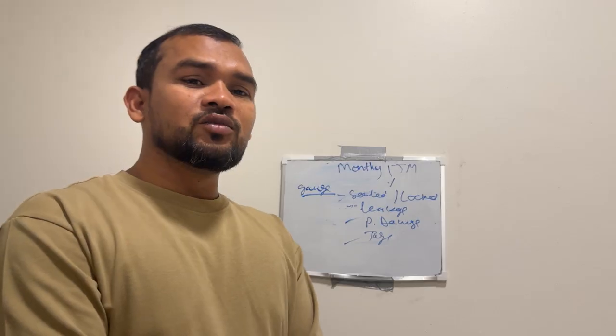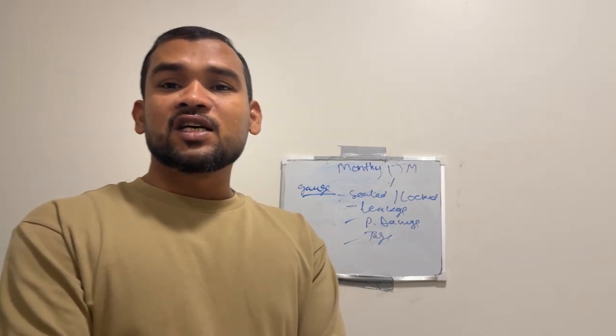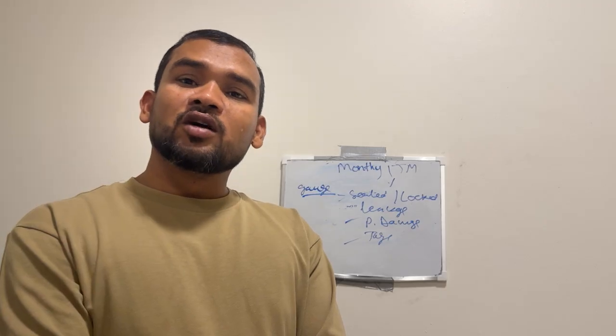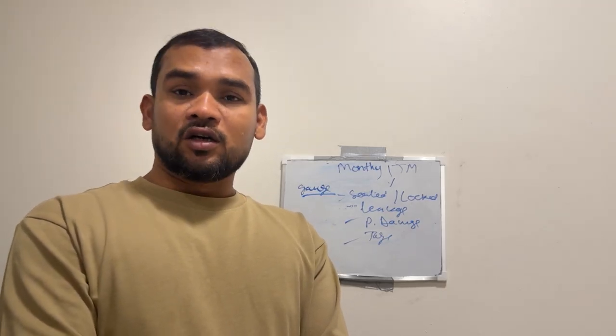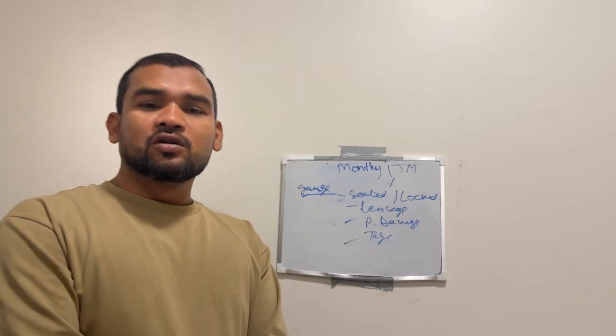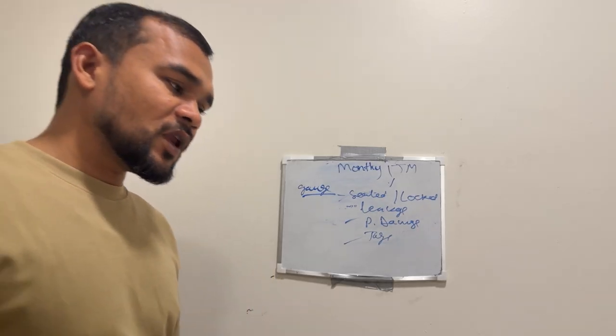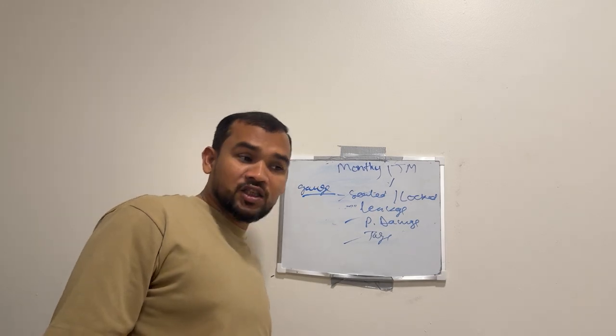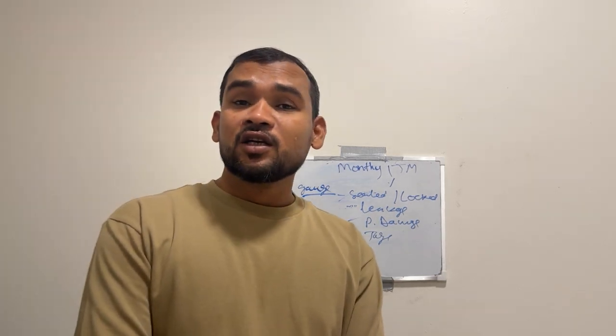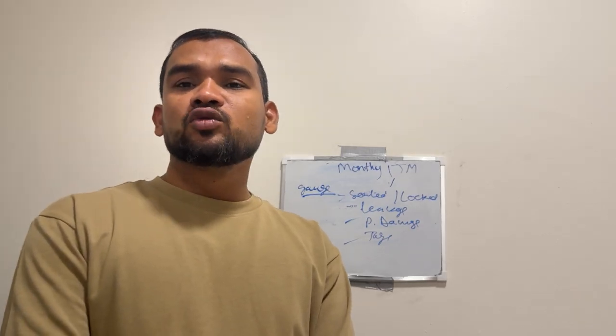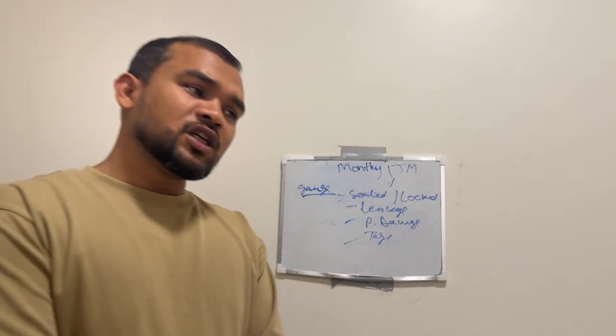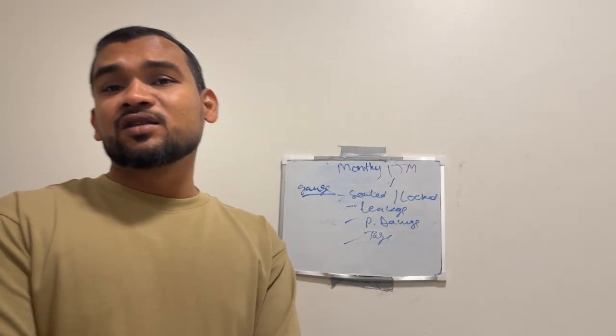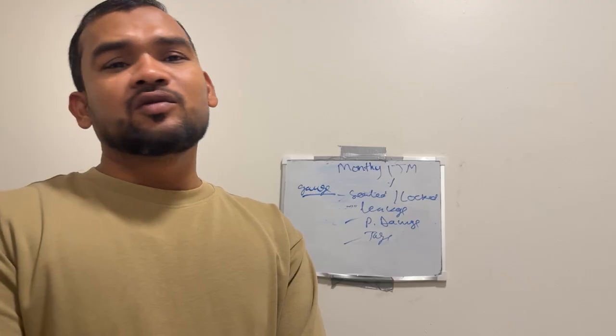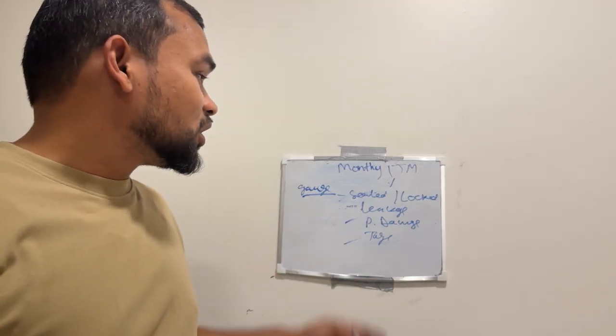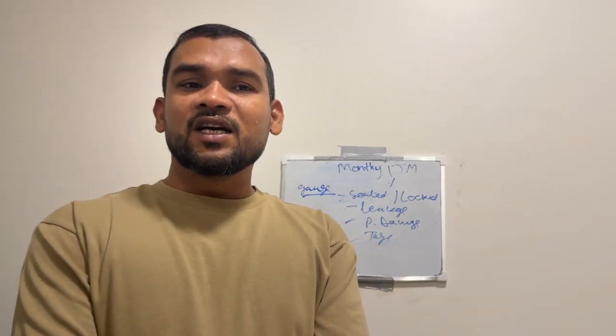For a deluge system, we have to check and note down the pressure gauge readings from the suction side and discharge side, the water pressure, and also the air pressure. That is the summary. We also have a monthly inspection for valves and their components. We check wet pipe, dry pipe, deluge, and pre-action systems on a monthly basis, checking the minimum requirements: leakage, physical damage, proper tags, valves sealed or locked, and supervised or not supervised.